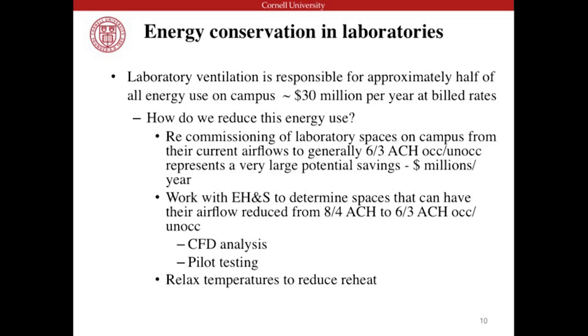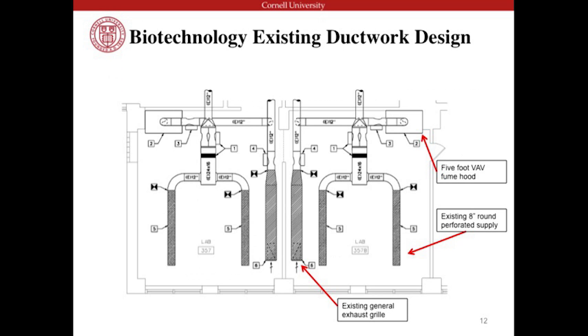The CFD analysis showed that in a smoke test, the smoke would stay close to the ground and wouldn't get flushed in a timely manner. What we found was that the supply duct layout — an 8-inch round perforated supply meant to create laminar flow from supply duct to exhaust duct to fume hood — didn't really work that way. The supply duct up at the ceiling was spitting out air that went right to the exhaust without hitting the lab space. So we said, well, I think we can do better.